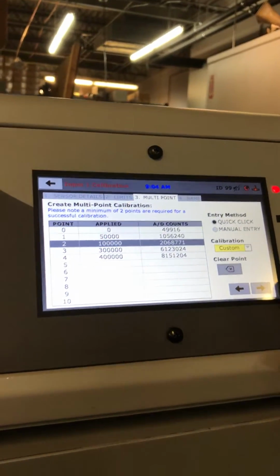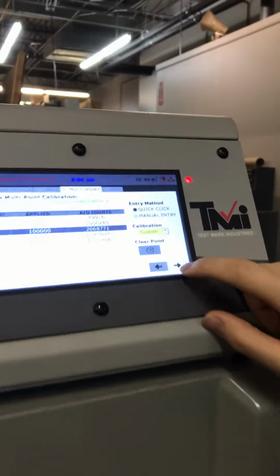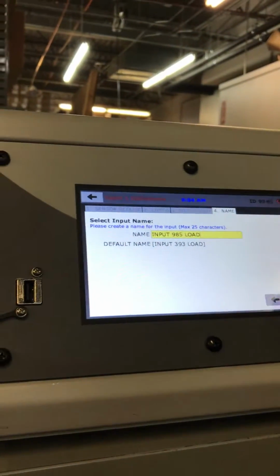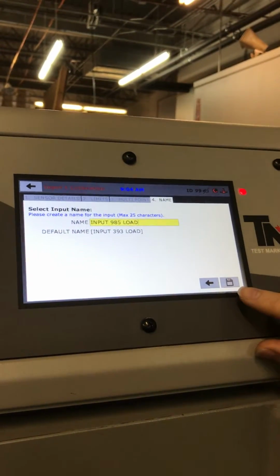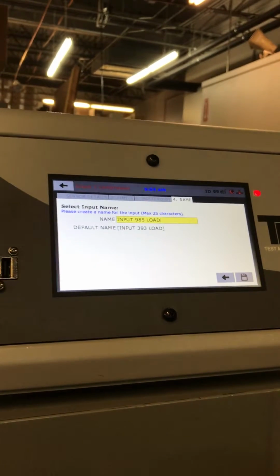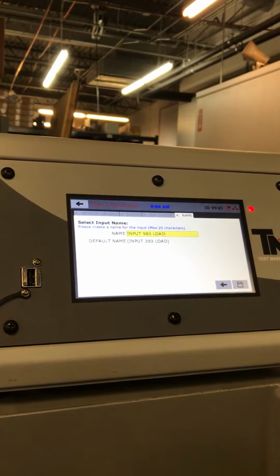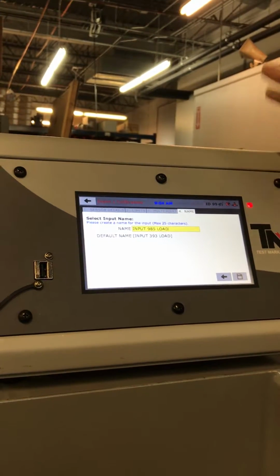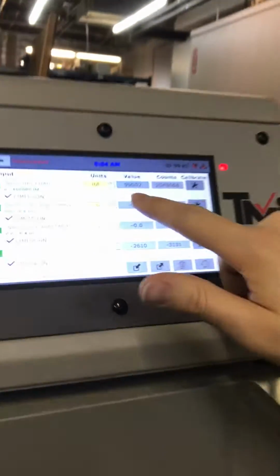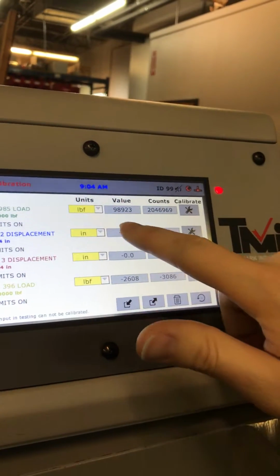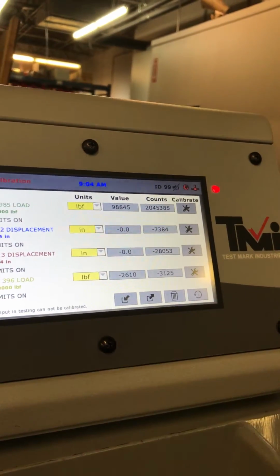And there we go. And then you can continue down the line, and when you're done, you just hit next, set a name for it, and hit the save button. And I don't want to delete my calibration, so I'm not going to do that this time. But and then you've got a calibration set, and it should show the correct values here for whatever units you have selected, and you should be good to go. There you go.